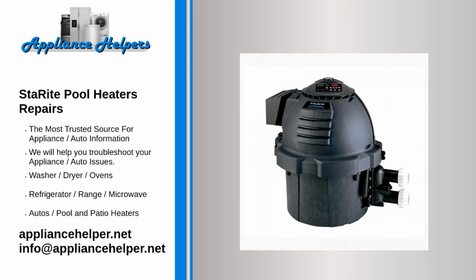Thermostat is set incorrectly or malfunctioning. Take a look at the heater thermostat on the unit itself, and if you are using a mobile or automated control, double check that it's set properly as well. Heater is too small. There are pool heater sizing calculations that will give you an idea if your heater has enough BTUs to keep your pool heated based on water volume and ambient air temperature.